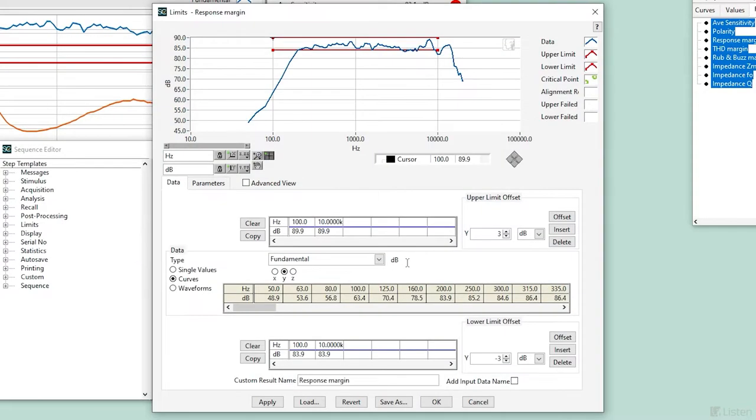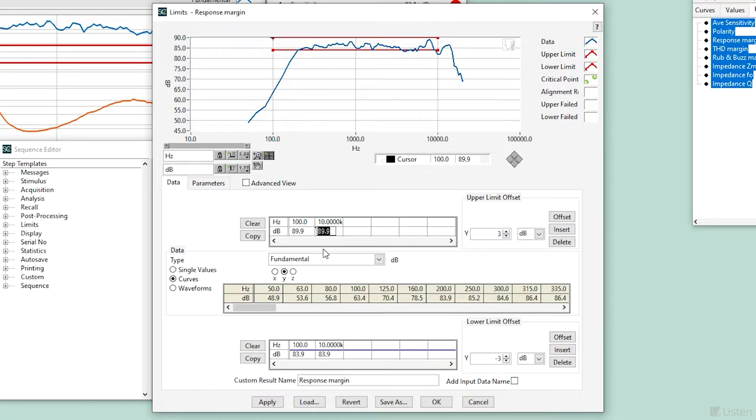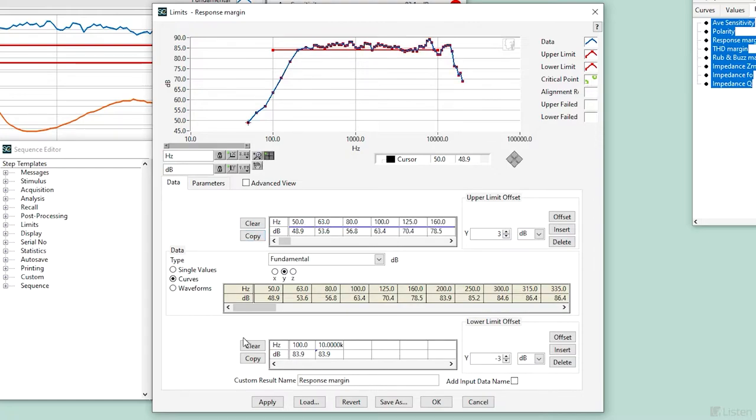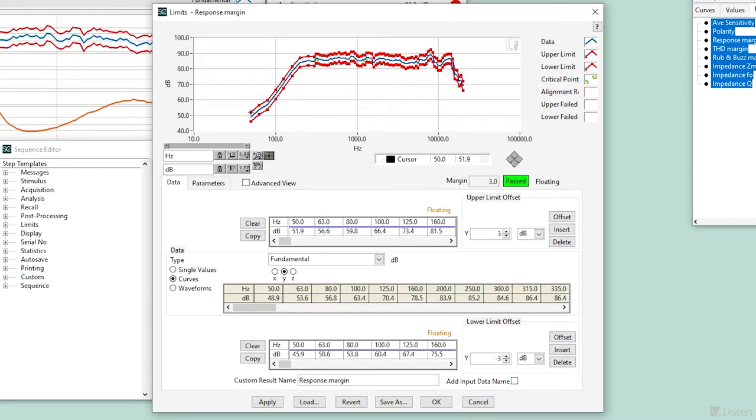Let's look at the limit step for the frequency response in this sequence. This is an example of a multipoint limit X and Y axis. I could edit either axis manually. Or I could use a curve from my memory list, set an upper threshold and lower threshold, and then apply the step.